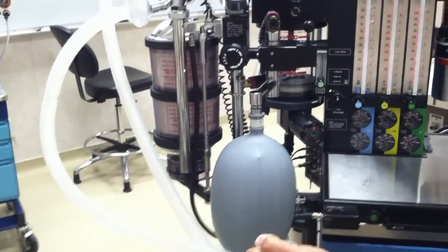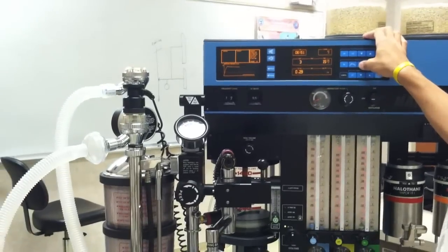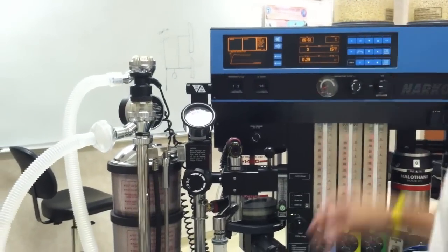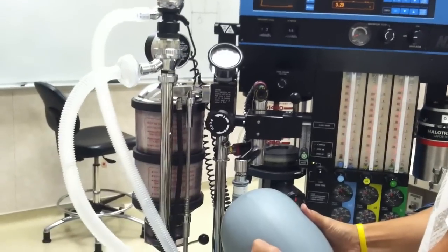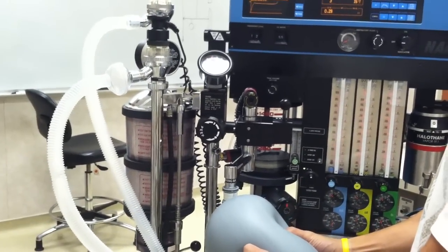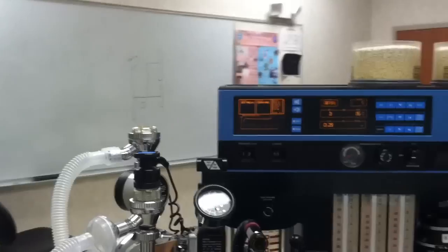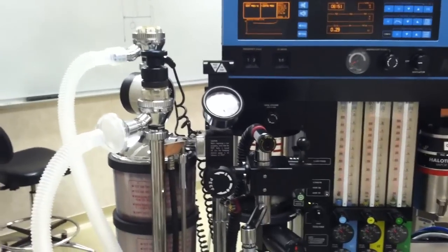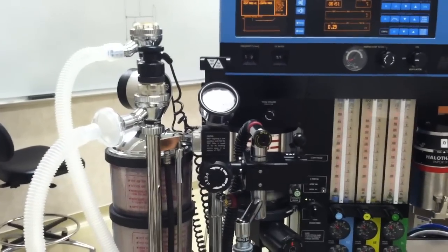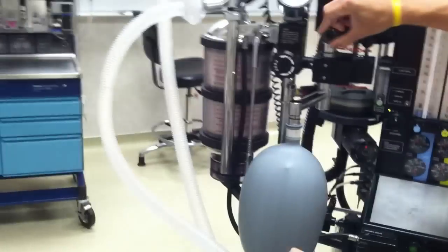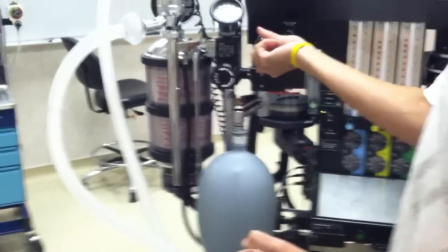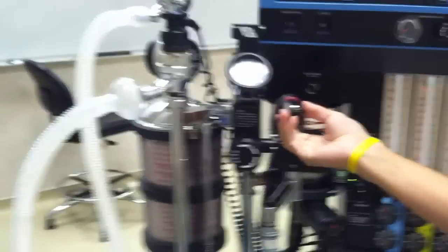And I'm going to go ahead and decrease this high alarm down to 40. Now I want to make sure that I hear two alarms, a sustained and a high pressure alarm. So there goes our high pressure and our sustained high pressure alarm. So we know that both of those alarms are working. We're going to open up the APL valve. It should go down slowly, open it all the way up.